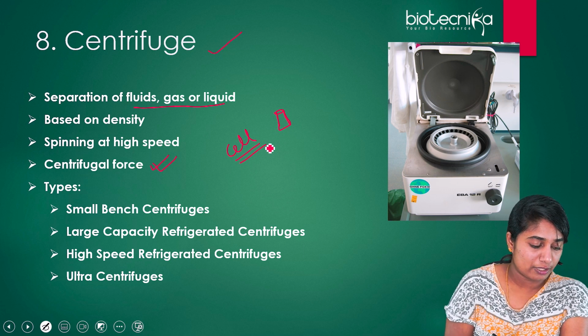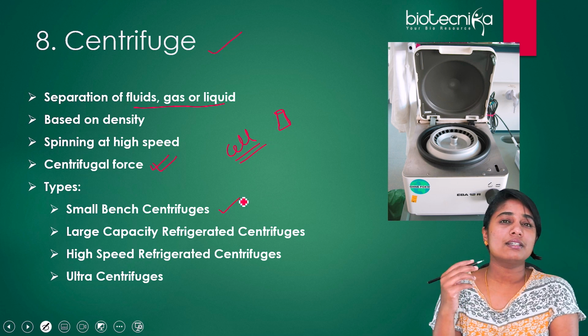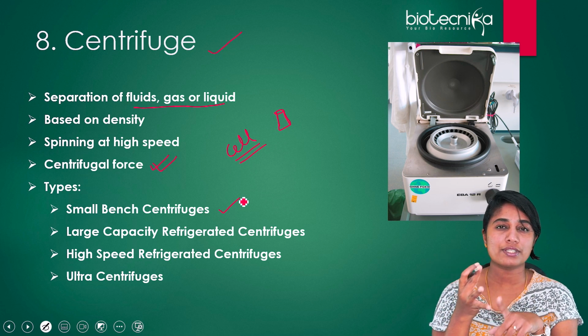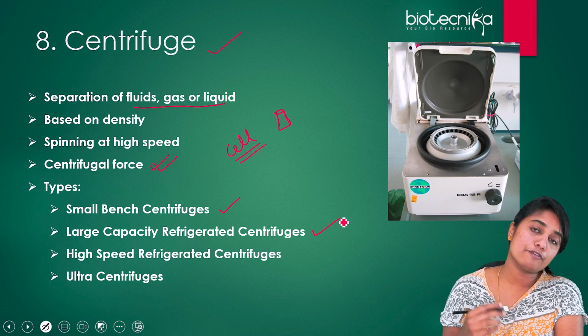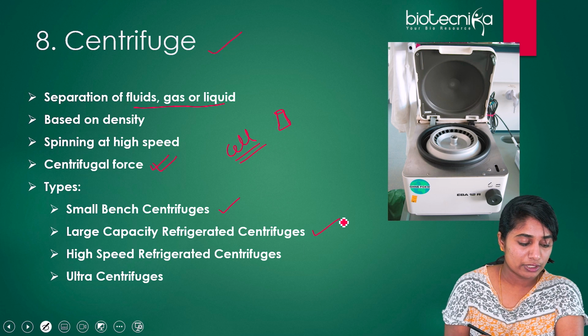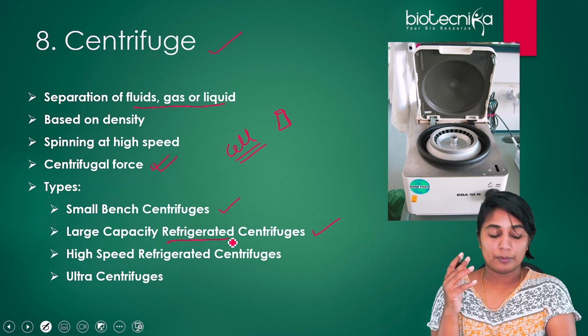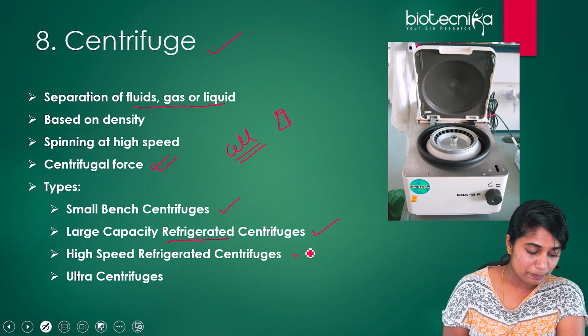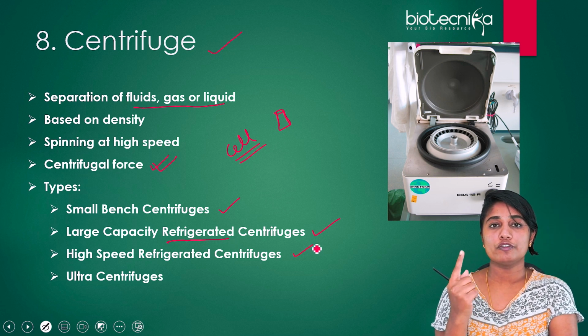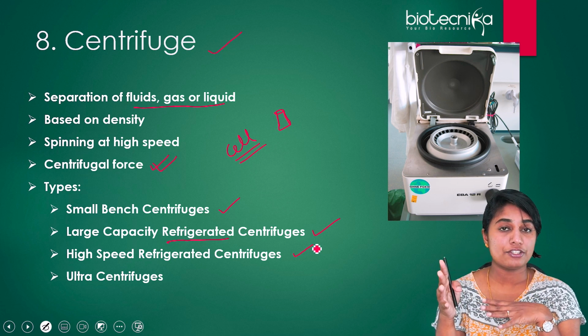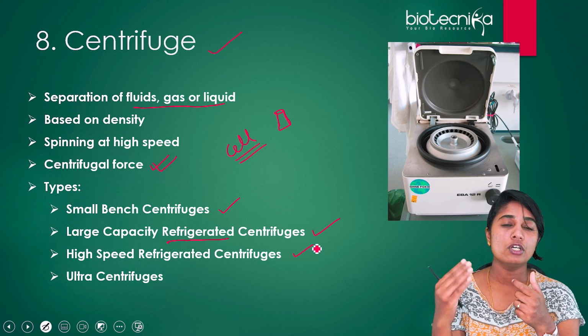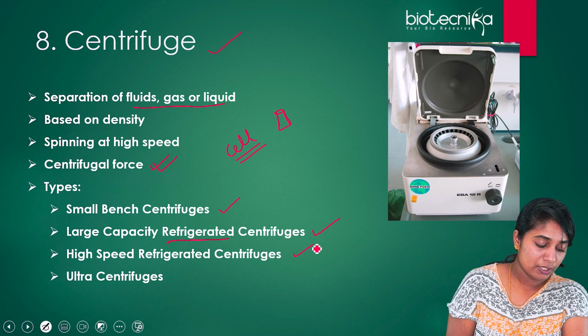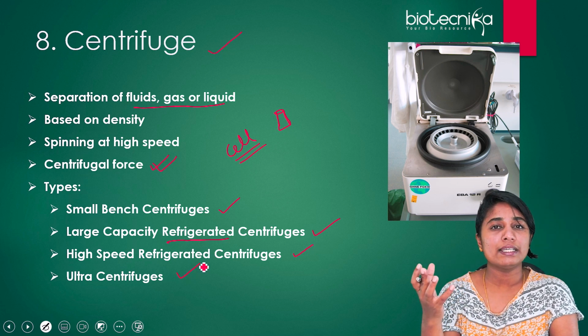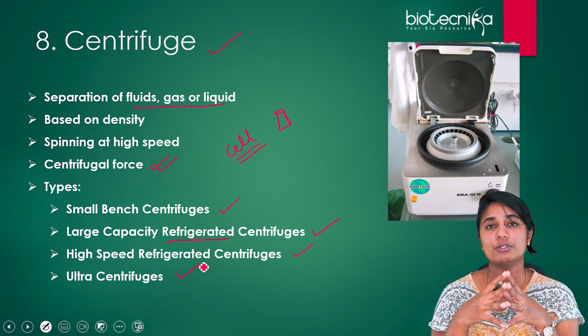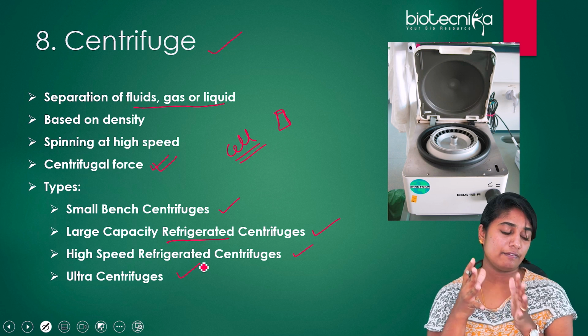Now, what are the different types of centrifuge that are found? First is a small bench centrifuge that is majorly used at the bench level. You use it for erythrocytes or for yeast cells. Second is the large capacity refrigerated centrifuge. As the name suggests, it has a higher capacity than a small bench centrifuge, and it has a refrigeration facility as well. The next is the high speed refrigerated centrifuge, where the speed of rotation of the rotor can be changed as well. There are different rotors that can be fixed to the centrifuge so that you have a variable speed of centrifugation. The last is the ultracentrifuge, which is used for more delicate molecules, where you have to separate them at a higher speed and in a very controlled environment.